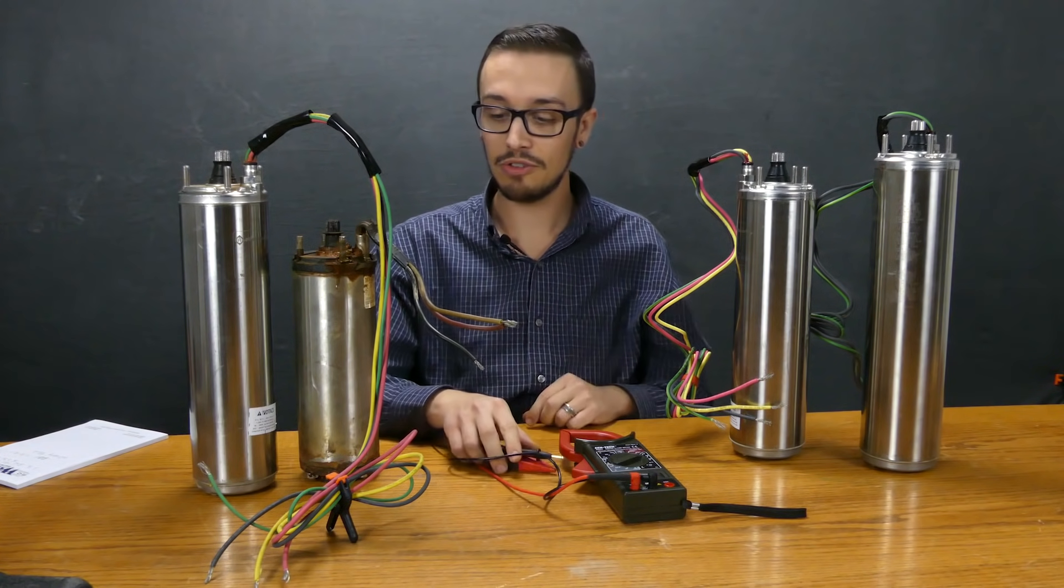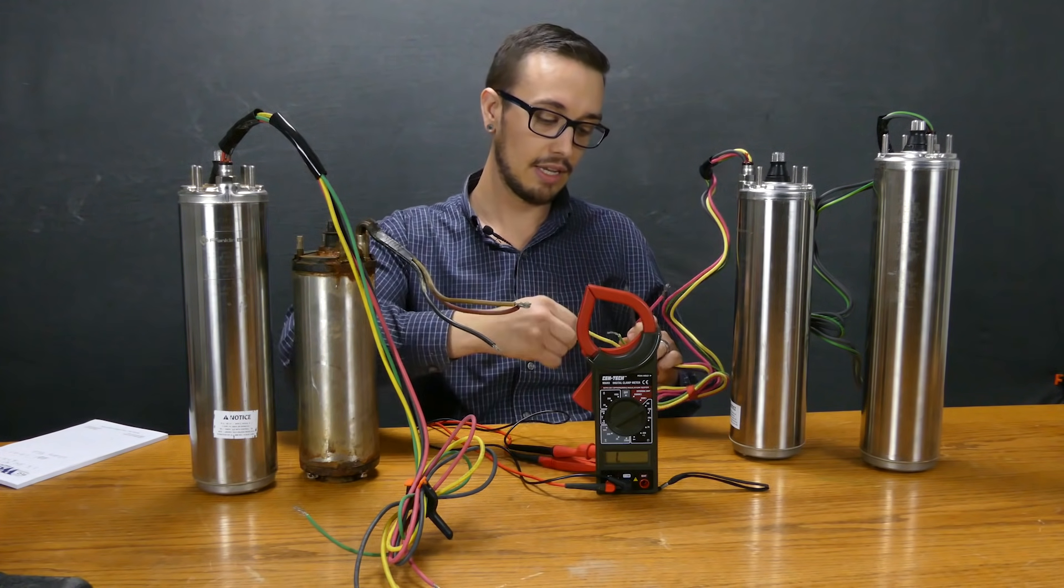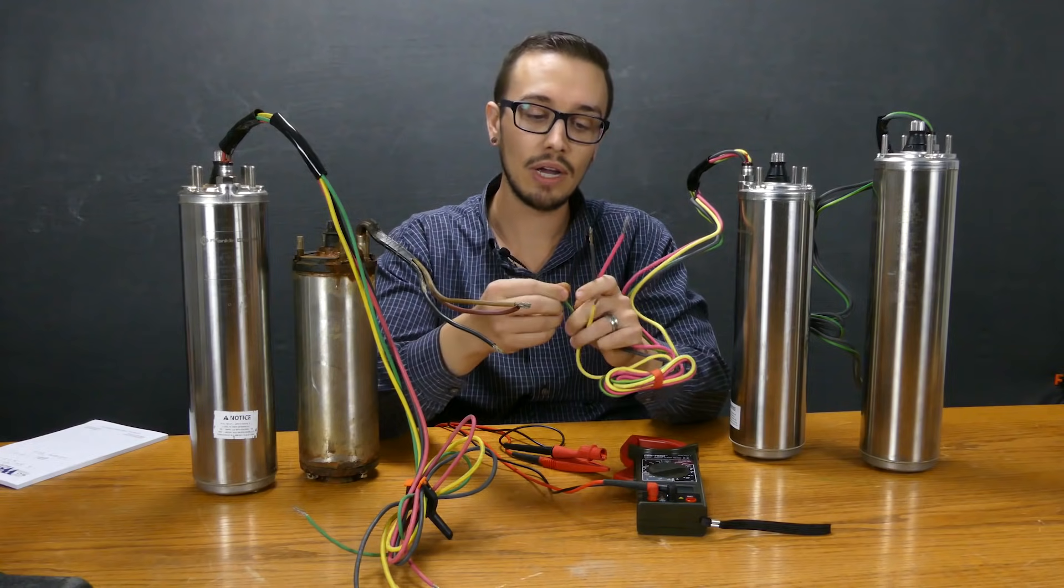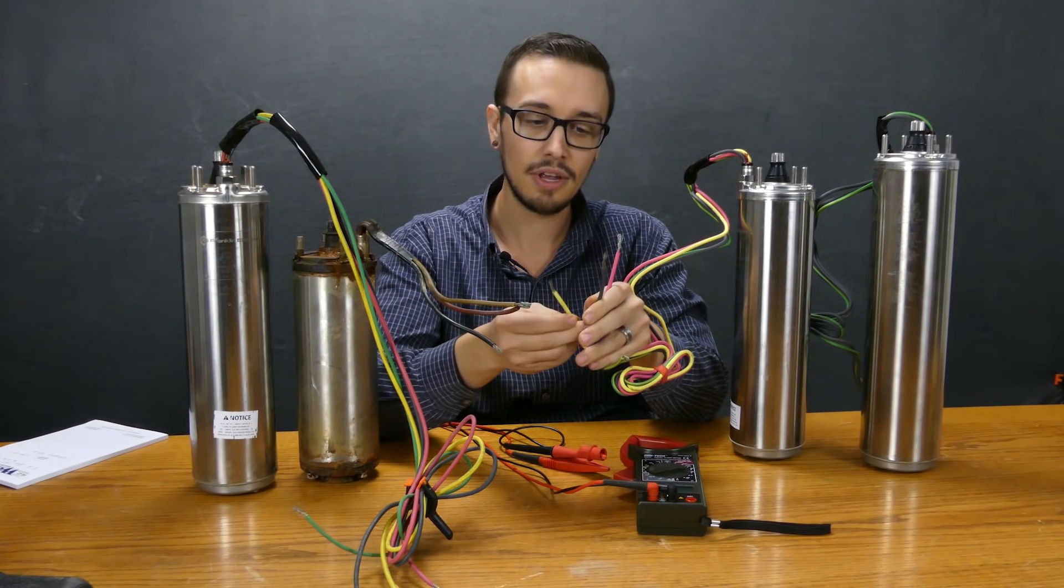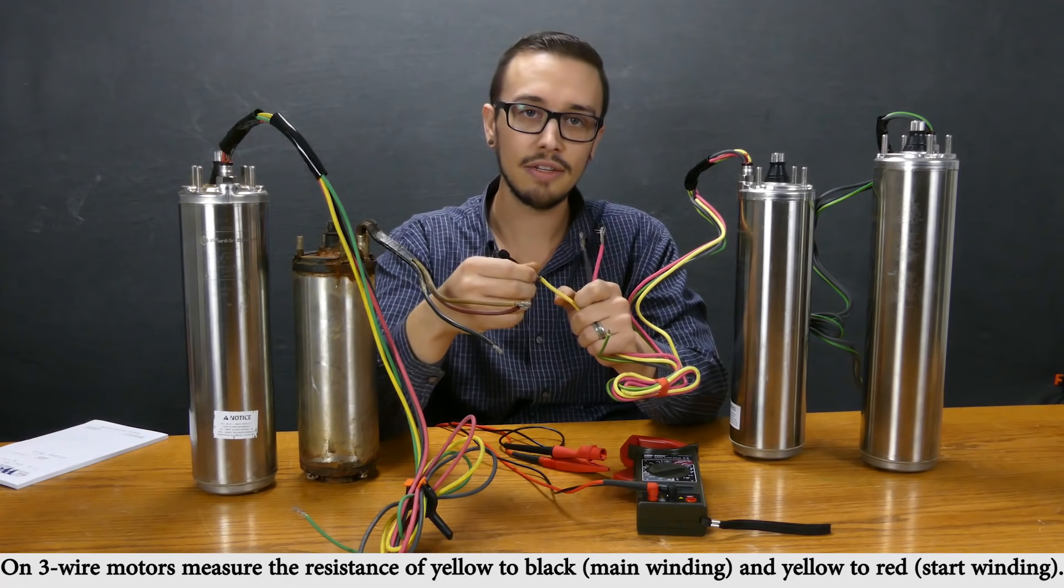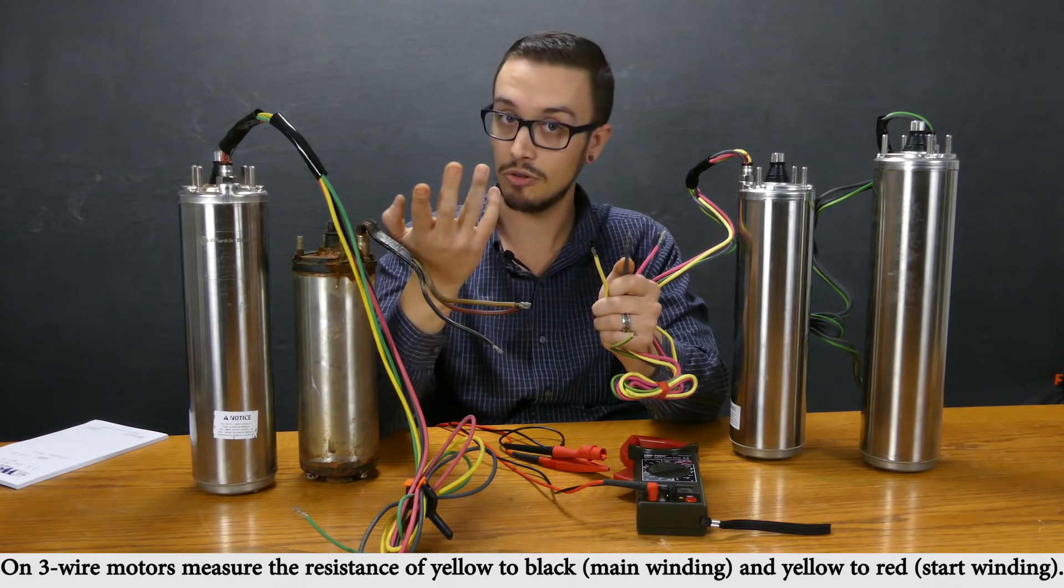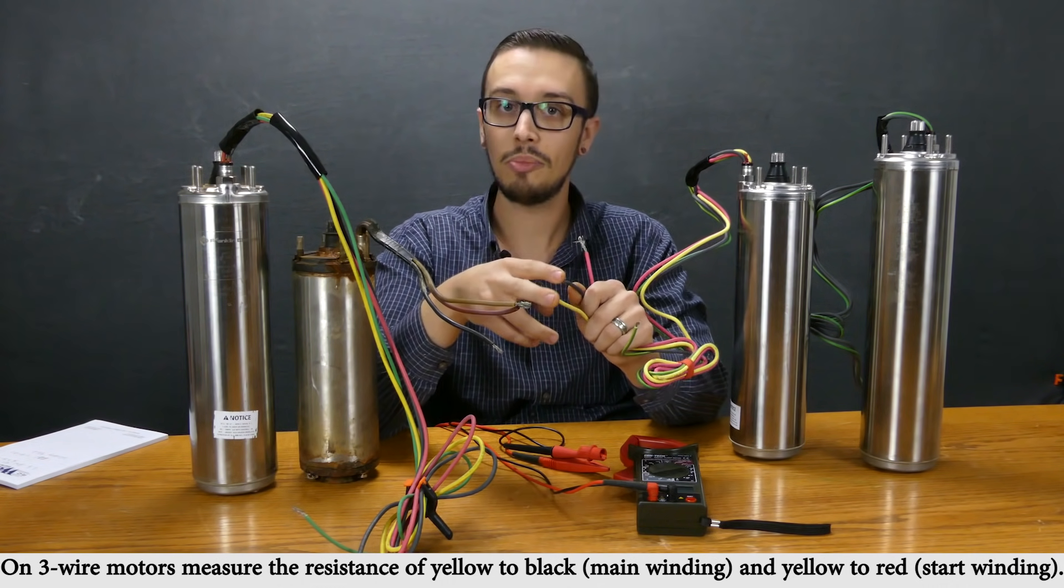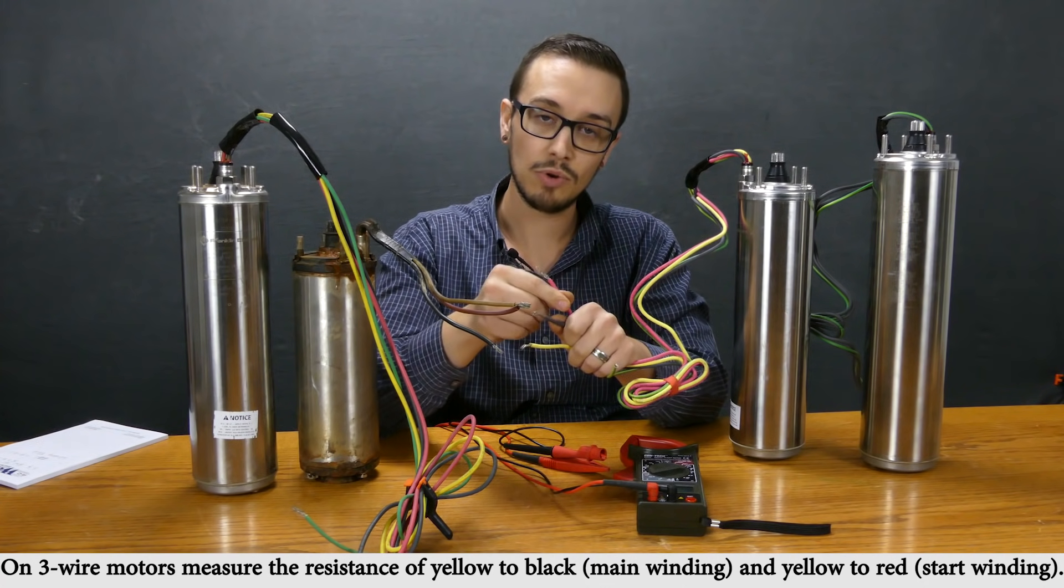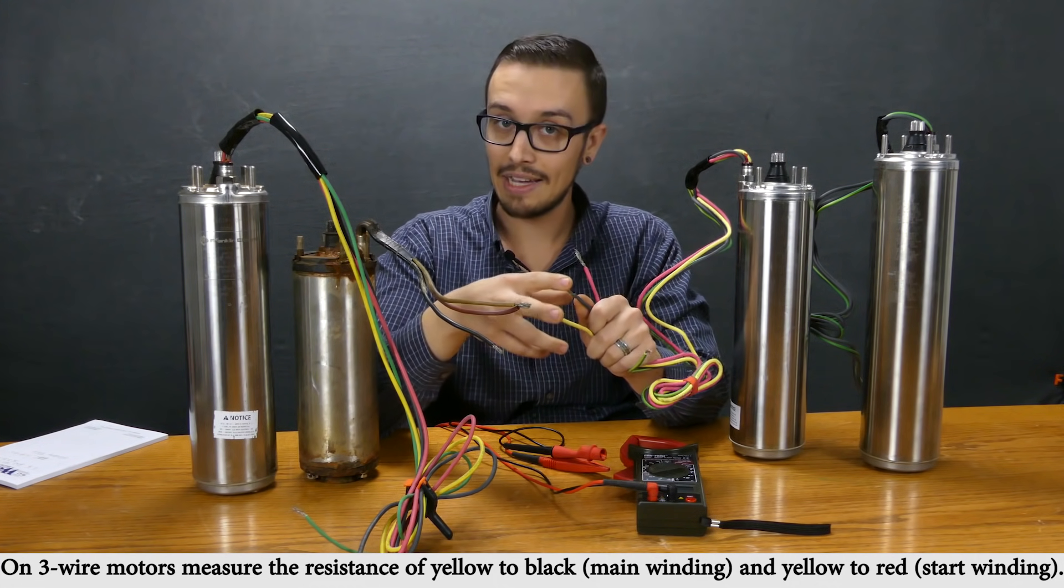We'll jump into the ohm test across the windings. When it comes to testing the ohm resistance between the windings we essentially don't need the ground for this test. We've got the yellow, the black and then the red. Yellow is your common line essentially. Black is going to be the main - so when the pump is up to speed or the motor's up to speed it's going to be relying on these two to power it. But on startup that's where that start capacitor comes into play.